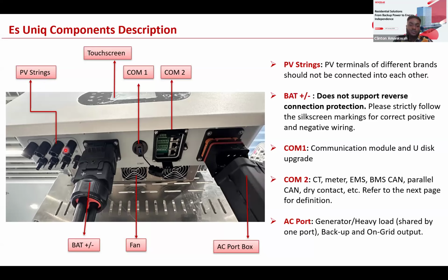And then you also have the battery slots. That's the battery inputs for your battery DC connection, where you can connect your DC main cables from the batteries to your inverter to supply DC power. And then you also have the cooling fan, for cooling of the inverter. Then you also have the COM1 port, which is basically for the connection of your Wi-Fi dongle kit to ensure cloud connectivity and data transmission for remote monitoring. Now, the COM2 port is another COM port where we make use of a parallel communication cable. So that's where you can connect your parallel communication cable, giving flexibility to connect up to a maximum of 6 inverters in parallel.